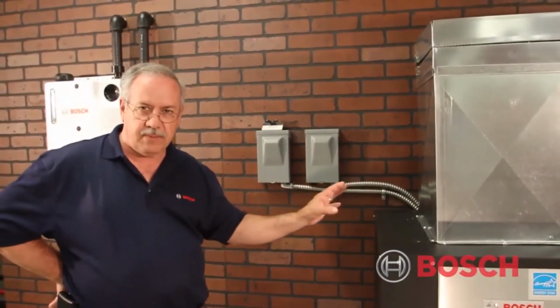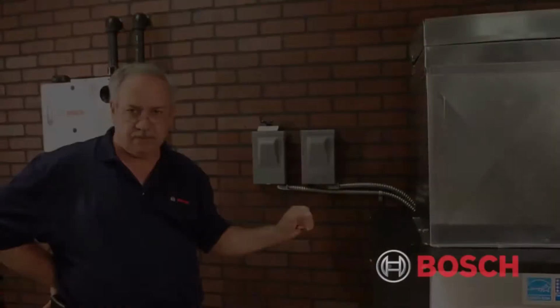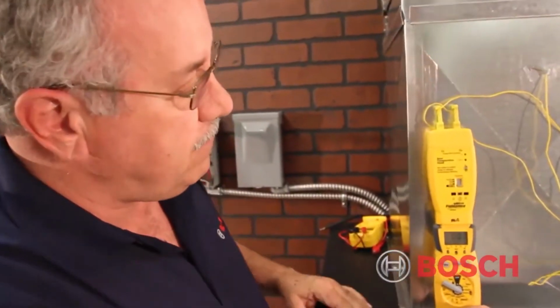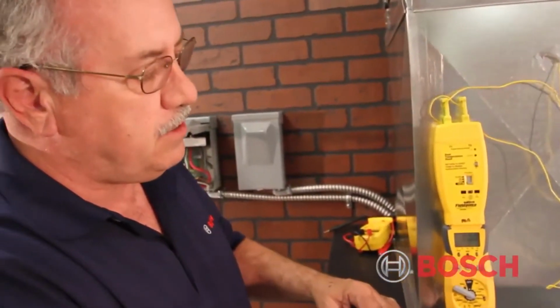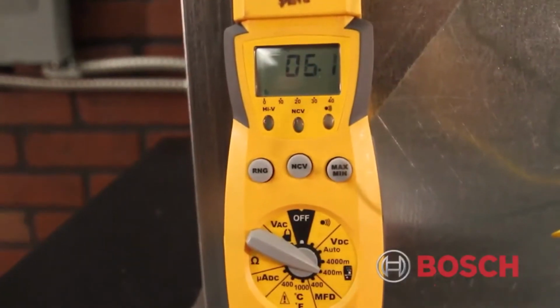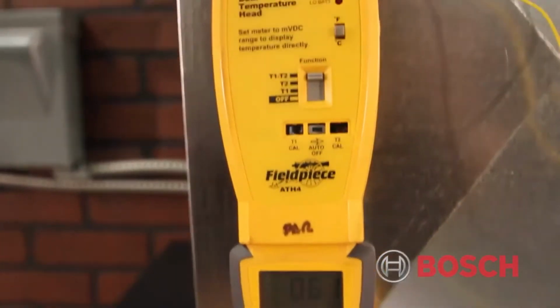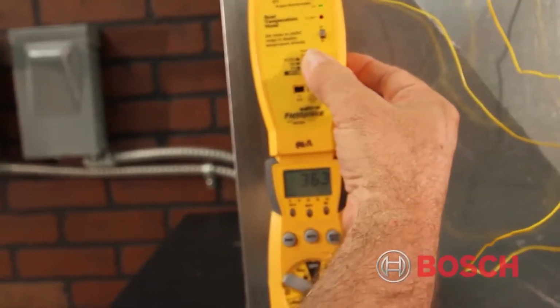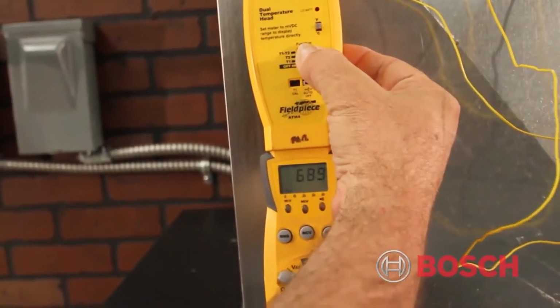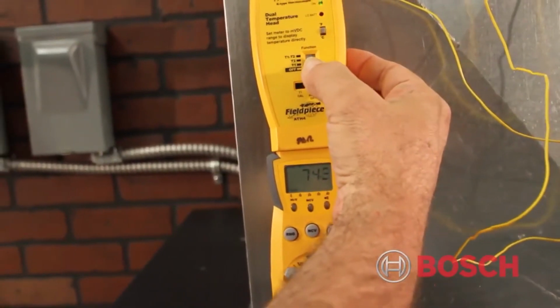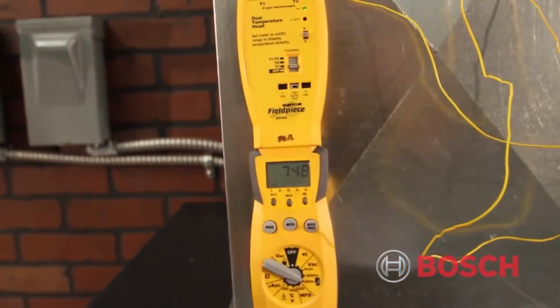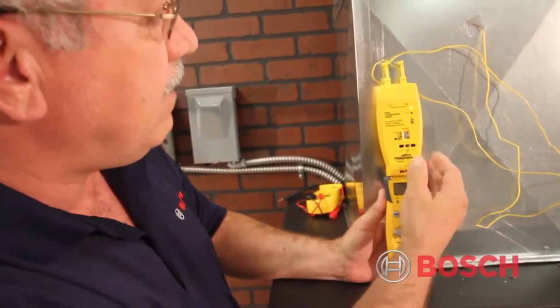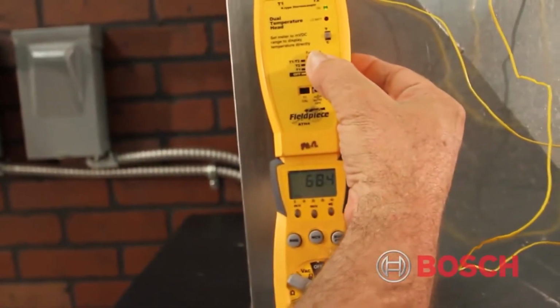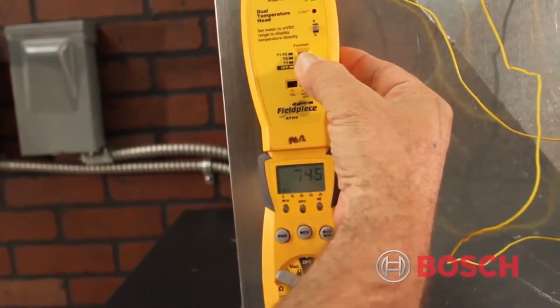So now we'll set up our tools to take the measurements. Okay, so what we've done is we've energized the heater in emergency heat in this particular TAO25. With my analyzer, with my thermistors in both supply and return, I can energize the dual heat control here, and I can see that one temperature is approximately 74 and a half degrees. The other thermistor is giving me about 68, 69 degrees.